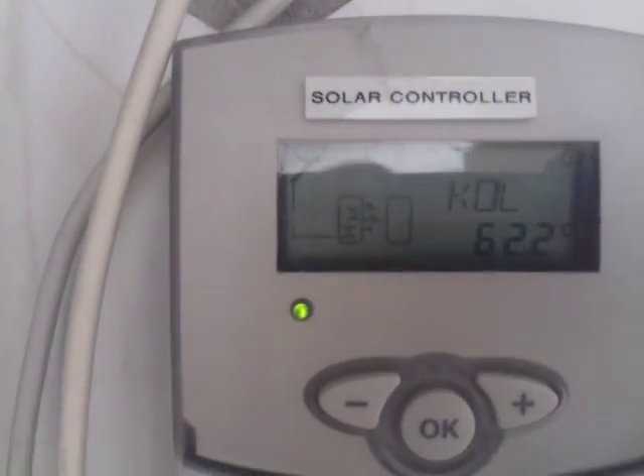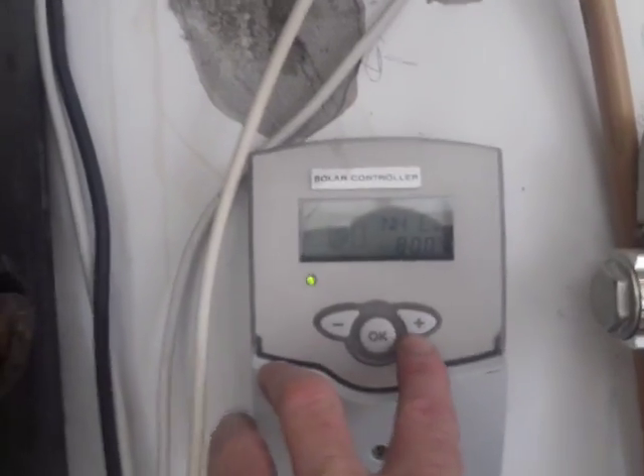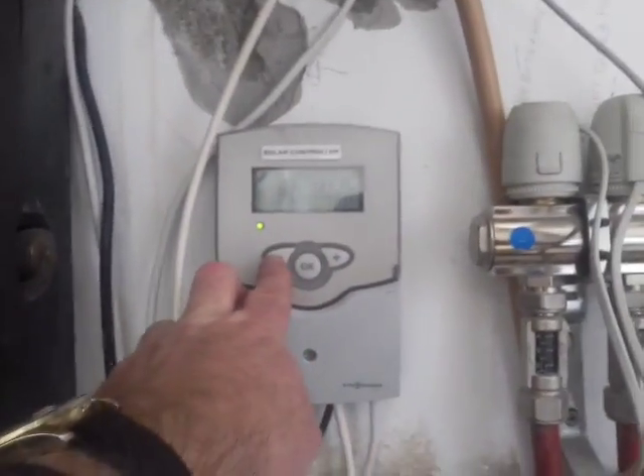There's a Viessmann controller controlling the solar, and the solar heats from the bottom up. It's also got a dump setting on it, which starts at 80 and stops dumping at 78, out to the buffer tank.